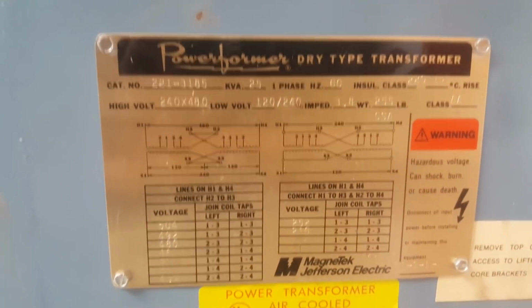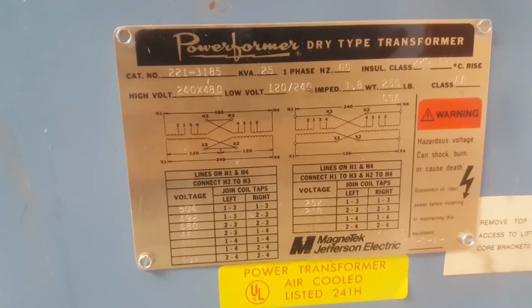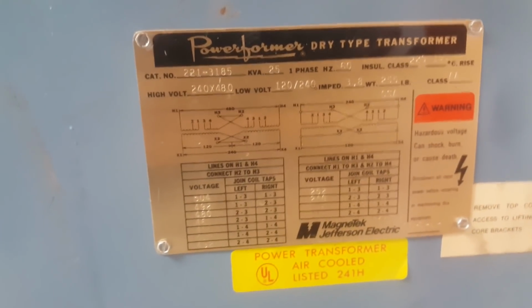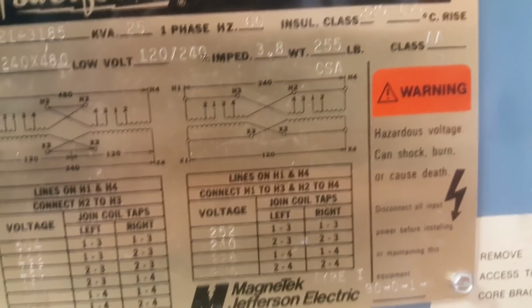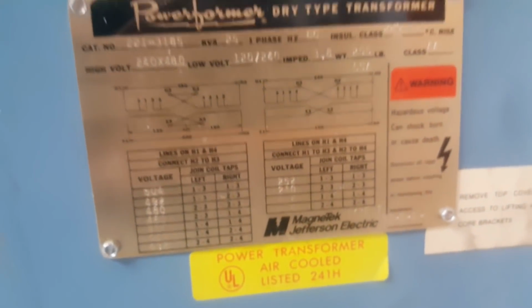They go through this liquid tight conduit to this transformer. Here is the nameplate on this. This is a 25 kVA. It's a step down transformer, but I have it run backwards for step up. Based on this wiring diagram, it pulls in 120 at the bottom and outputs 240 volts single phase at the top with no neutral.